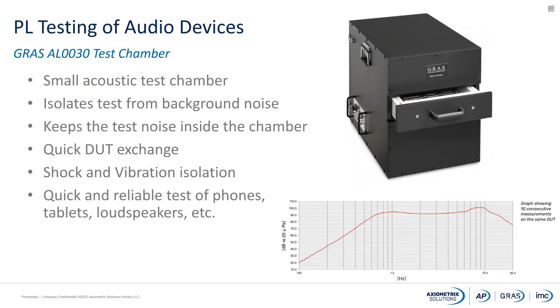Here we can see more pictures of the AL30. As we can see in this picture over here, on the back of the AL30, we have a big opening. Inside, we have acoustical dampening foam that will help reducing the amount of acoustical reflections inside the chamber. When we open the door, it's going to be easier for the operator to set up equipment inside the test chamber.